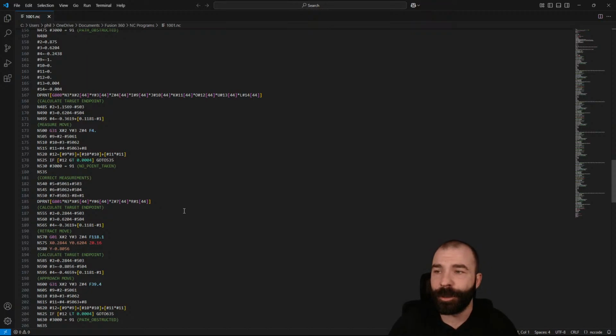So that you don't, again, your first time through in commissioning, smash your probe. And if you guys have ever seen it, there's these little rings people sell now that is probably the most genius thing ever—best thing you could 3D print to put on that stylus. So you hit the ring on your probe first, and that will alarm your probe out.